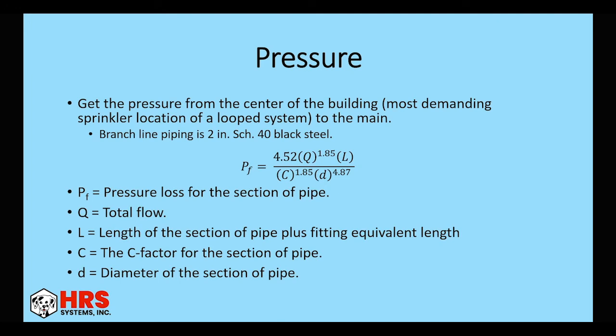So then we want to get our starting pressure, which is obviously our flow out of an individual sprinkler over our K-factor squared. So for this example, it's 24 divided by 8 squared to give us 9 PSI. From there, we use the Hazen-Williams. We're going to say our branch lines are 2-inch Schedule 40 black steel. Again, this is a seismic zone. So we didn't want to go over 2-inch. So we didn't have to brace as much. So again, just normal Hazen-Williams formula.